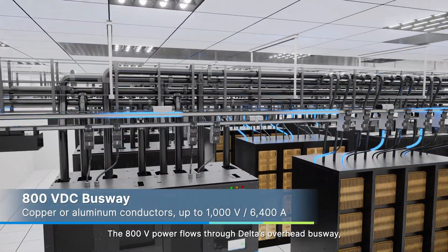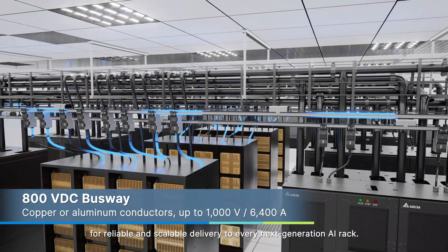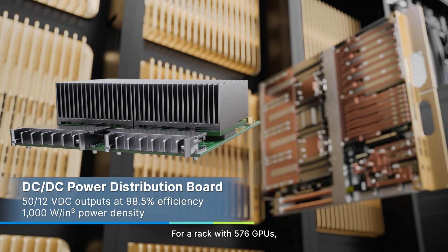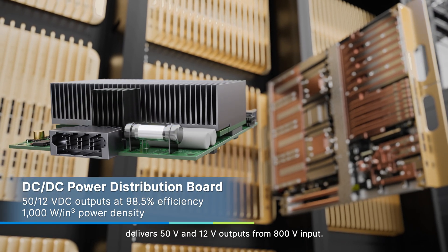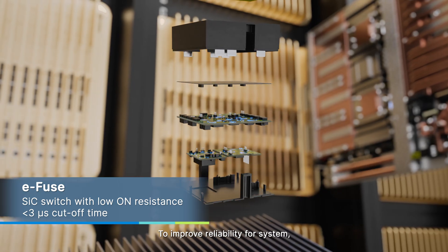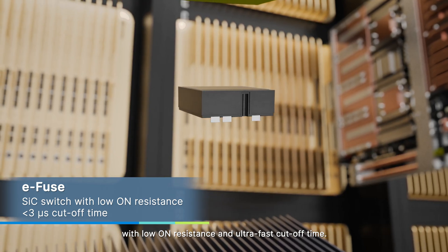The 800 volts power flows through Delta's overhead busway, using copper or aluminum conductors for reliable and scalable delivery to every next-generation AI rack. For a rack with 576 GPUs, Delta's compact DC-DC power distribution board delivers 50 volts and 12 volts outputs from 800 volts input. To improve reliability, Delta offers a compact e-Fuse silicon carbide-based switch with low on-resistance and ultra-fast cutoff time.